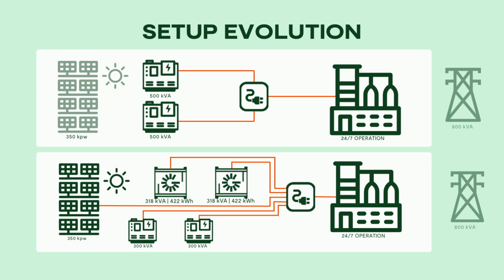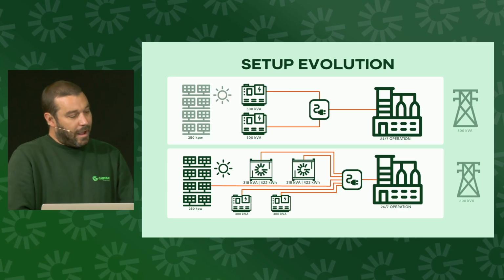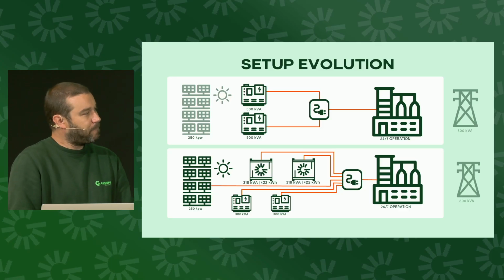The reason being, we now have somewhere for any excess energy that's not being consumed by the load to go, and that is into the batteries to recharge them. And we also managed to control the solar array and reduce the amount of power produced by the solar when the batteries are full. Yes. If the battery was becoming fully charged or was reading 90%, then Greener's EMS was curtailing that solar array, just turning the power production back, so as to avoid overcharging the batteries, which would initiate a shutdown on the batteries, because, for similar reasons to the generators, there's nowhere for that energy to go.